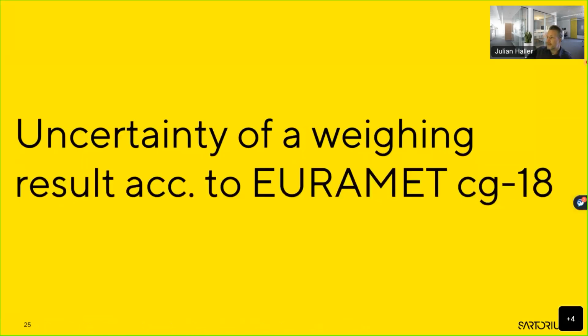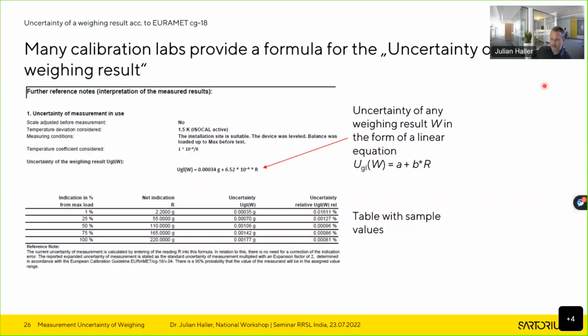And that is actually the topic of the next part, the uncertainty of a weighing result for the user, according to this calibration guide. Now, let me start with demonstrating how we, and of course also other calibration labs, give that information. So this is again part of a calibration certificate, how we issue that all over the world. We give as further reference notes, additionally to the calibration result, information about the uncertainty of measurement in use or uncertainty of any weighing result. And this is usually, according to the calibration guidelines, stated in the shape of a straight line equation. And we provide a table with sample values.